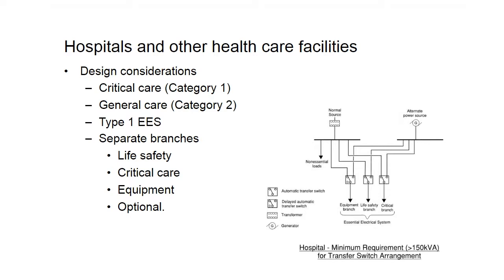The other two branches that are required by code are the critical care branch. This serves primarily patient care focused loads, oftentimes imaging equipment, receptacles, small equipment that's required for patient care. The equipment branch is predominantly three-phase mechanical loads, so air handling units, boilers or heating systems, medical gas pumps, vacuum pumps, things of that nature would fall into the equipment branch.